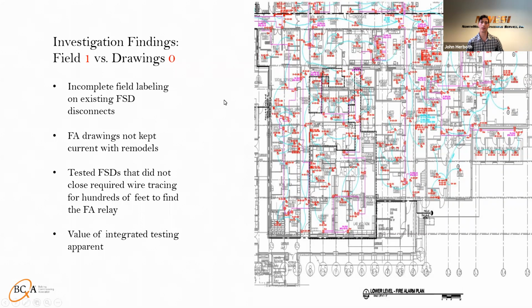Drawings for fire alarm aren't something that I know that I initially looked at as commissioning provider very closely, and now I look much closer at it, specifically that they've identified where those relays are located, which is often near an electrical panel, and usually just outside of them, but sometimes not. So those end up being really important in a hospital level, especially, or any other building where the testing can get complicated because of what they do. And popping your head above every ceiling tile is just generally not great.